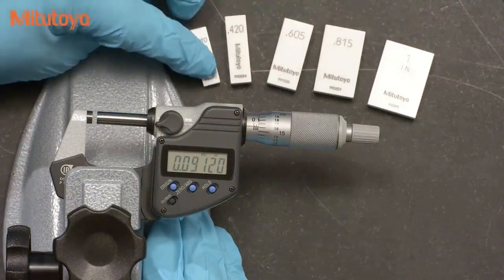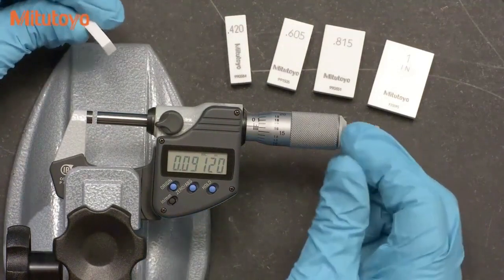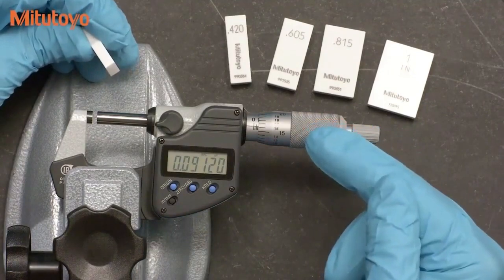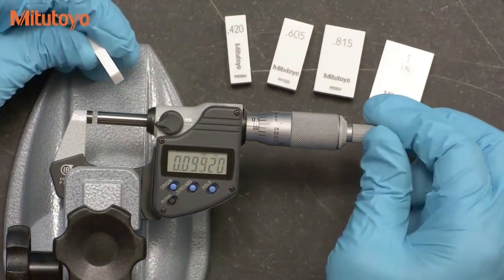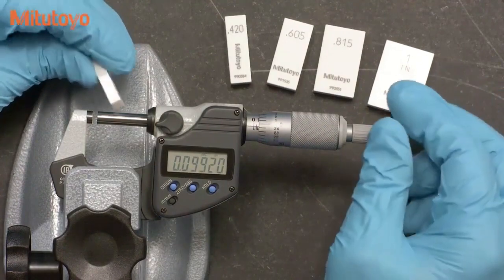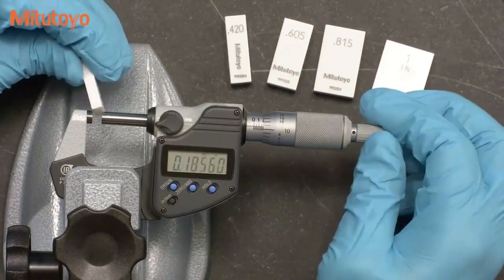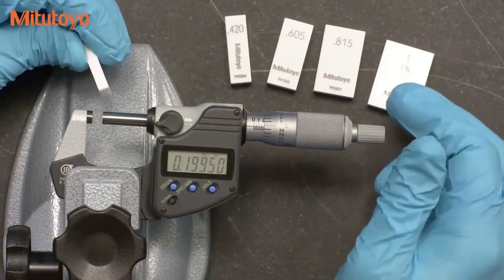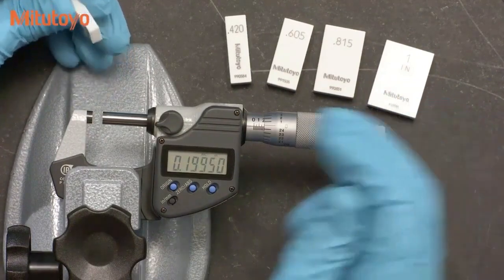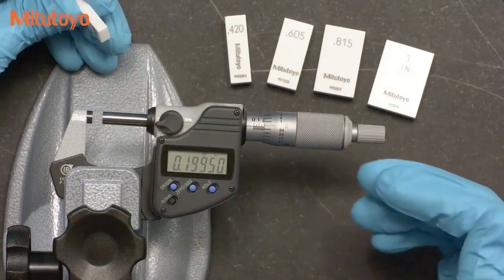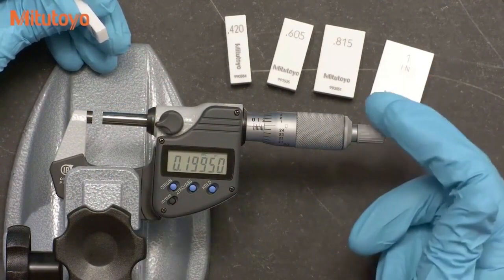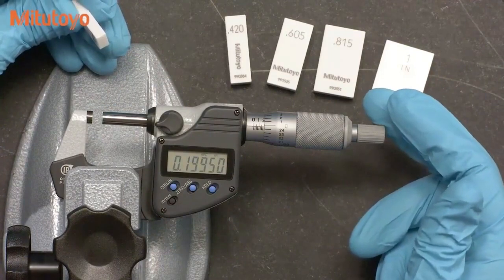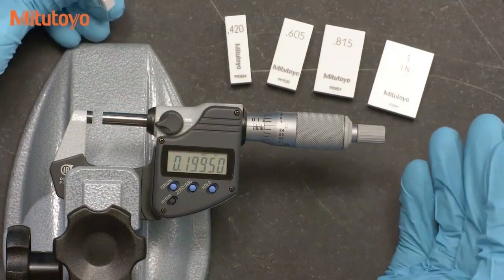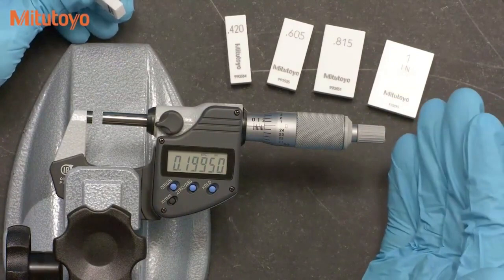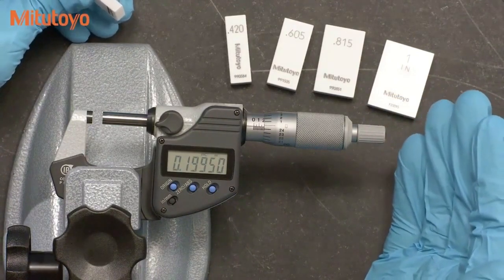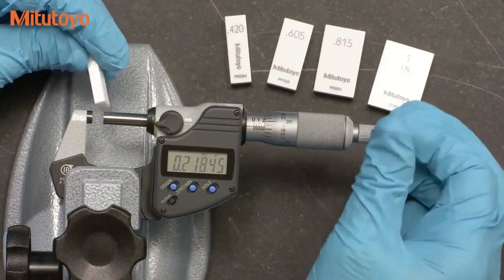The reason for these specific sizes is that they will force the micrometer thimble to be in different orientations for each test point. Remember that the goal of a good calibration method is to have an efficient test, and the use of these 5 test points will look for errors across the measuring range simultaneously with the rotation of the thimble. These 5 blocks are the most efficient test, but if you don't have these special sizes, you can choose to use others that achieve the same goal. The principle is what is important, not these specific sizes.